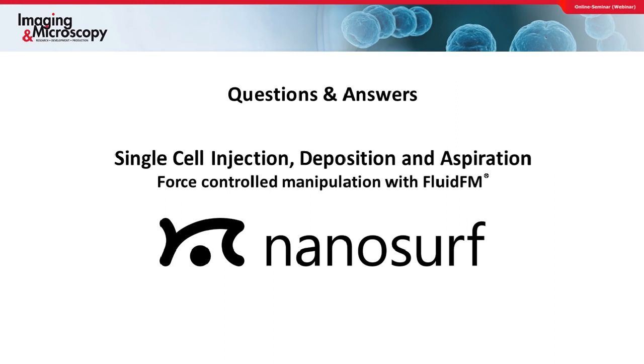Our first question is, does the probe get damaged when it touches a cell or substrate, or does it damage the sample? I'll answer this one if you don't mind. The probe is on a cantilevered spring that will bend upward when it makes contact with the cell. This reduces stress on the cell and prevents damage. In addition, the forces that are applied are very, very low, so there's very little stress on that cell.